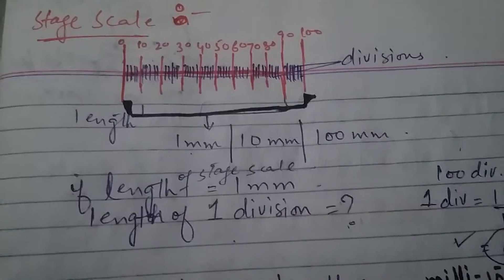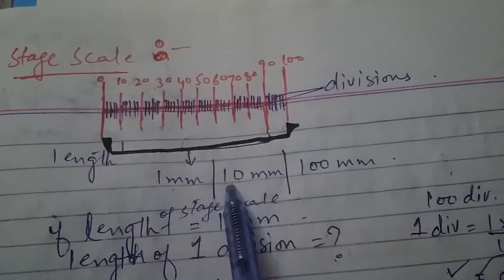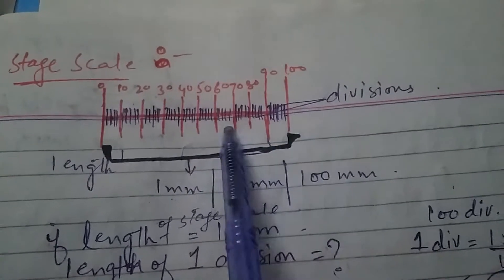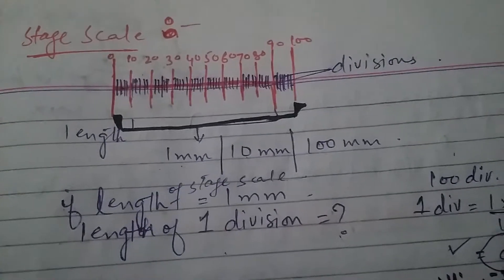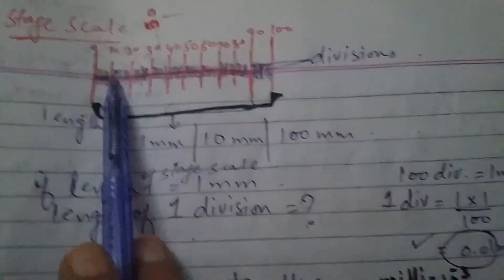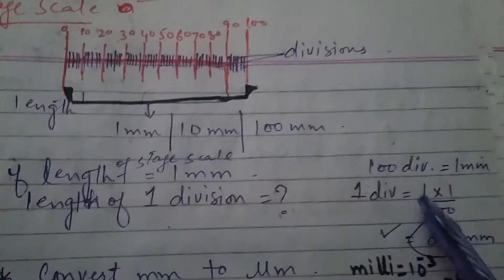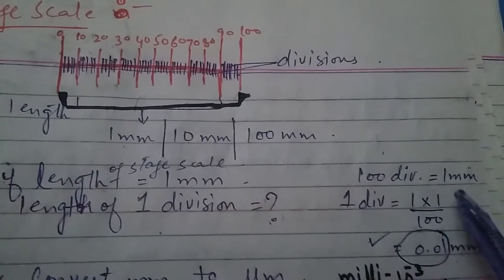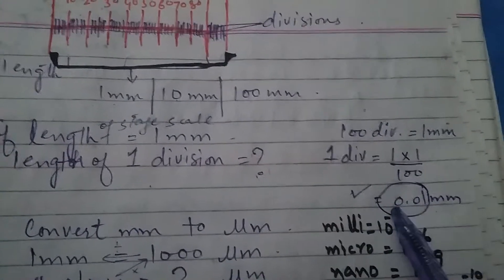Now, this is the stage scale. The scale can be 1 mm, or 10 mm, or 100 mm. If the length of the stage scale is 1 mm and it has 100 divisions, then 100 divisions equals 1 mm. Therefore, 1 division equals 1 divided by 100, which gives us 0.01 mm. So the length of one division of the stage micrometer is 0.01 mm.